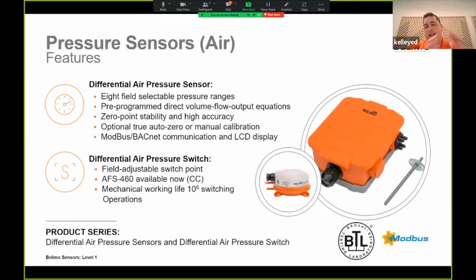Jumping over here to pressure. The image on the right is one of our pressure transmitters. These are available in BACnet and Modbus, and analog as well. As we know, with most of the offerings out in the field, you've got a zeroing feature where you pop the cap open and push a button to zero it out during the calibration sequence. With critical applications, we're seeing these have to get calibrated roughly once or twice a year. In the more non-critical applications, these get calibrated about once every 2 years.